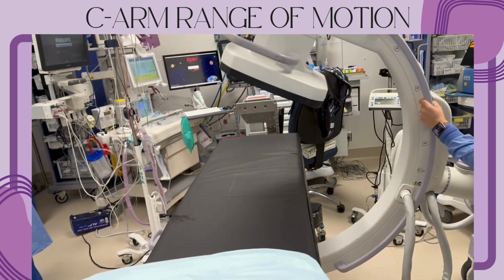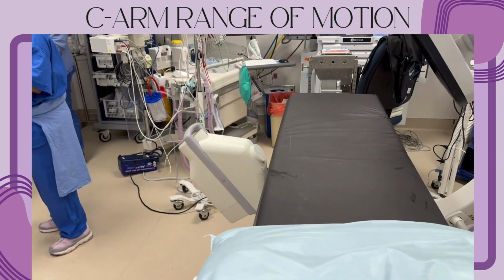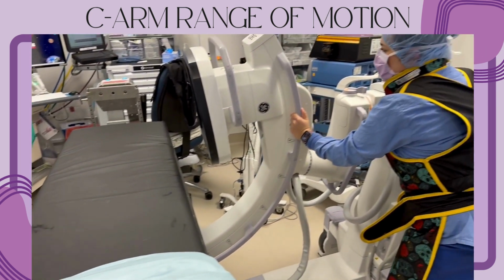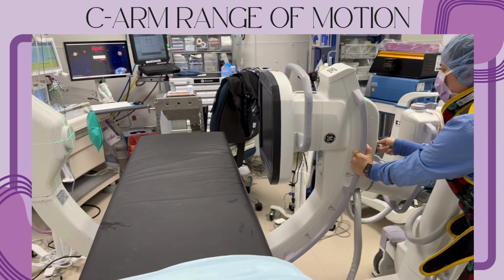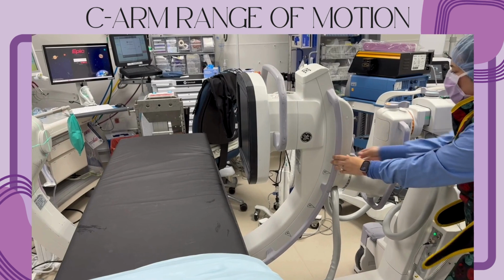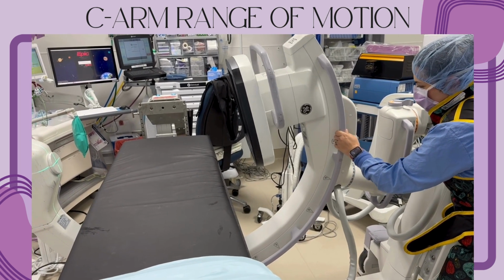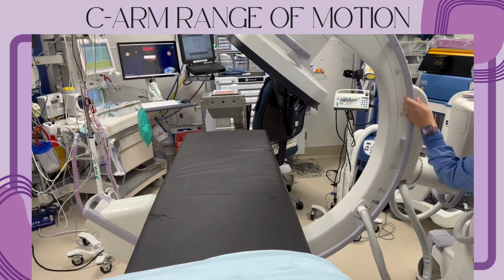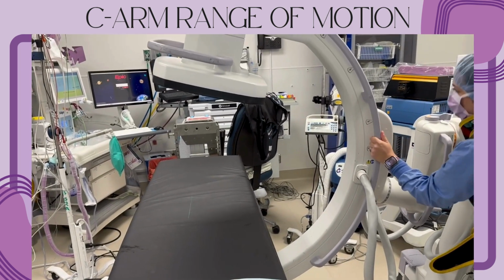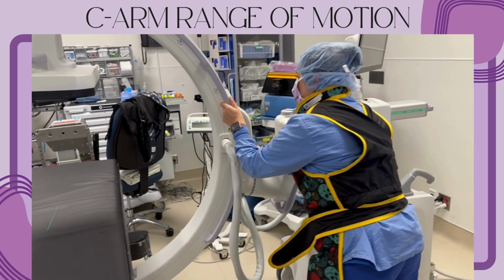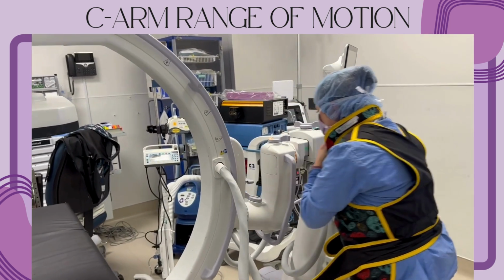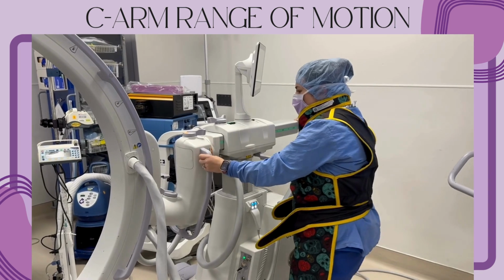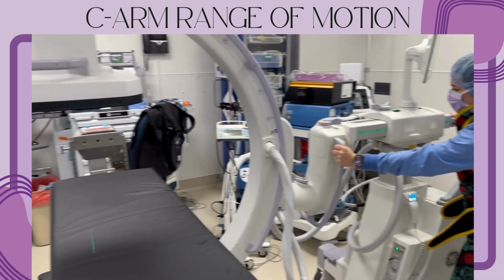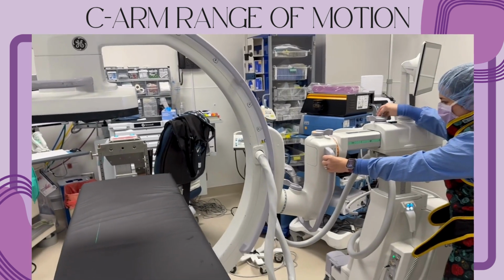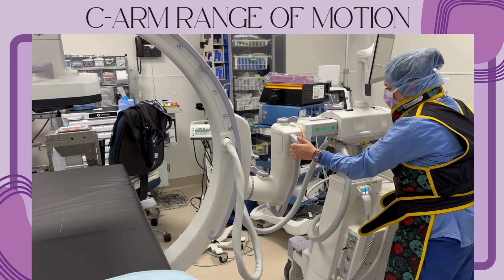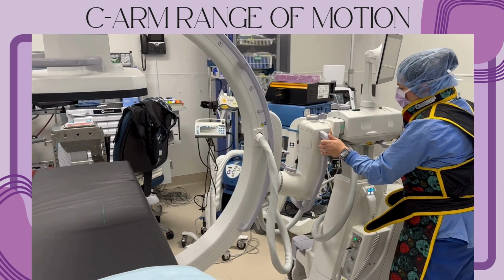The blue lock allows us to move the C-arm to a lateral or an oblique position and back to an AP, and typically we call this rainbowing. So as you can see, while I'm doing this, I am moving the tube up and down so that I can ensure that I don't hit the table. The next lock that we have is the green lock, and this green lock allows us to move the C-arm in and out. This makes it especially helpful for centering.